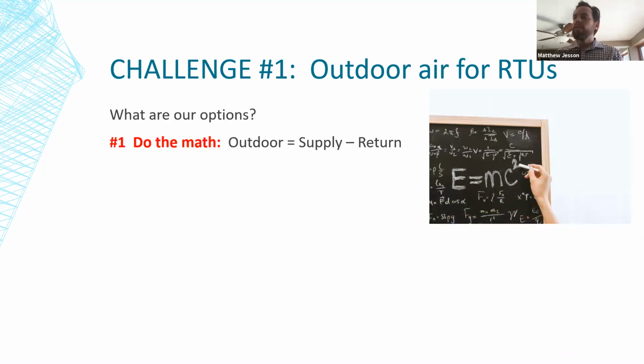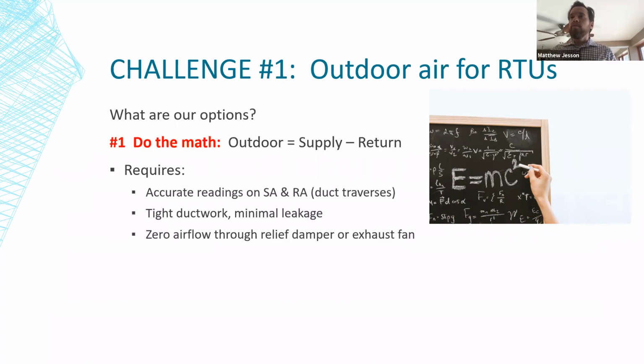But what are our options? So the first one is arithmetic. Your outdoor air should be the difference between your supply air and return air, right? That's pretty straightforward and true. What you need in order to use that method are, first of all, accurate readings on your supply and return air, by which I mean good duct traverses.